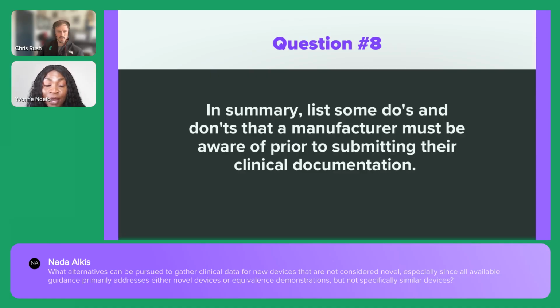I think, from my perspective, new devices are kind of easier, because with legacy devices the challenge is trying to get all that data. With new devices, I would assume this is a device that is not in the market. In that case, I would say you need to go back to the MDR. It depends on your class. Get your classification right, so that you can choose the right clinical evaluation route. Obviously, if you're a high-risk device, you might choose some of the evaluation routes in Article 61. And then make sure that you have also read MedDev 2.7.1 Rev 4. That's what would help you determine what kind of clinical evidence is enough, as a new device, based on the type of your device.